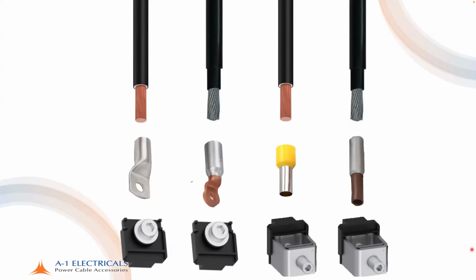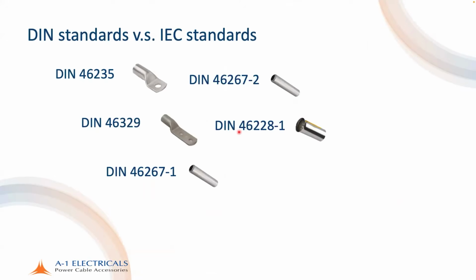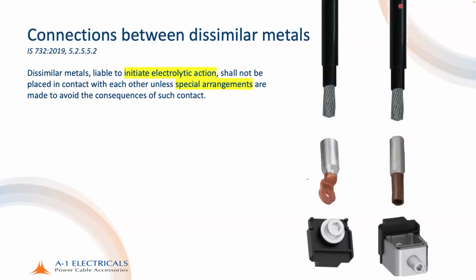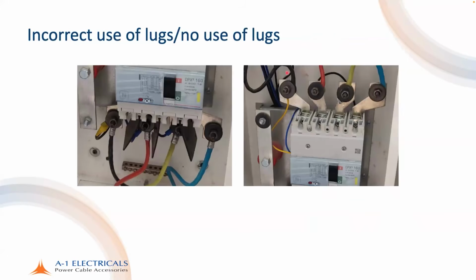And the tool has to be also according to that. So there are various DIN standards and IEC standards, and you need to identify which one. I don't know what is widely being used, because honestly speaking, we see a lot of poor practices, where a connection is not made correctly, and oftentimes, unfortunately, an aluminum conductor is just brought in. In fact, I remember in Bangalore, I did one event with NFE, and somebody came up to me and said, in my 40 years of career, I have never heard of bimetallic lugs. So that is quite shocking. So yes, it is there.